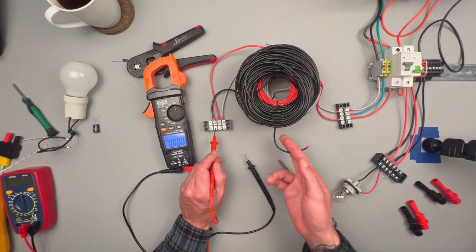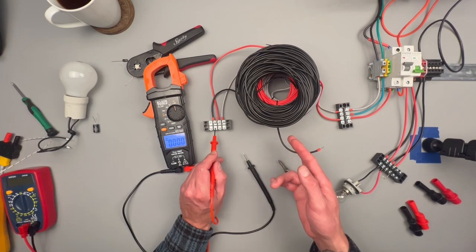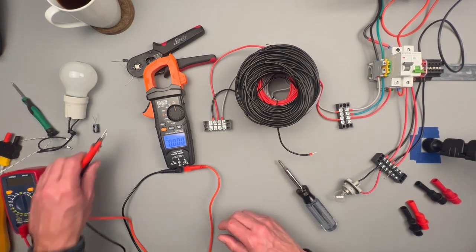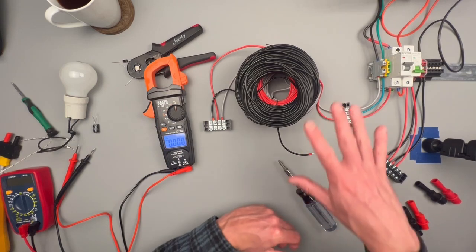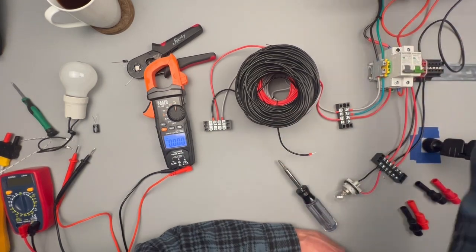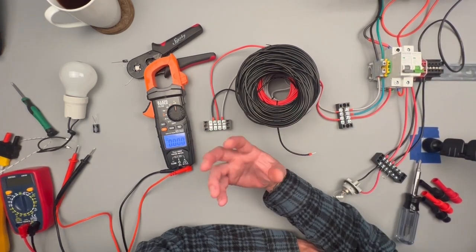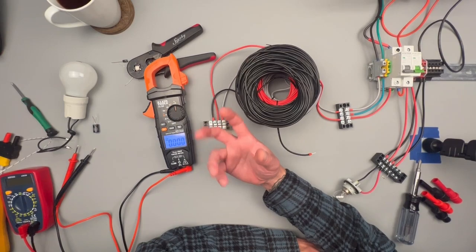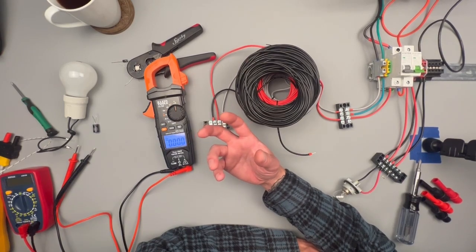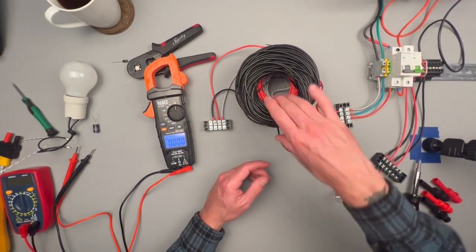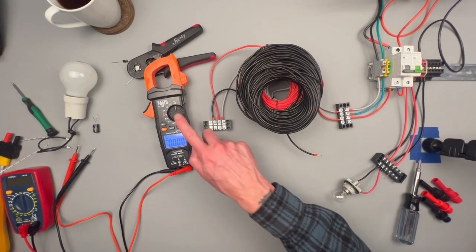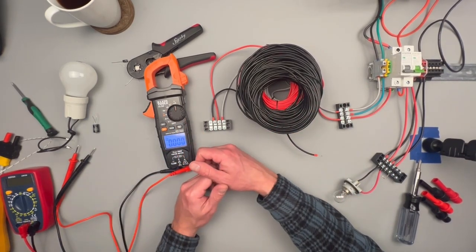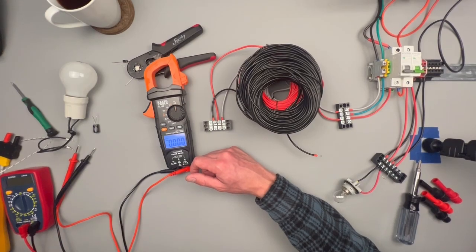That's because there's no usable voltage. The other side of this black wire isn't actually hooked up to anything. So that's going to be really handy for troubleshooting AC circuits over long distances. When you have those long AC runs that run in parallel, you're going to get a lot of induction onto the surrounding wires. And so if you have a dead circuit surrounded by live circuits, it's going to be full of that ghost voltage. That low impedance setting on this meter is really handy for sniffing that out.